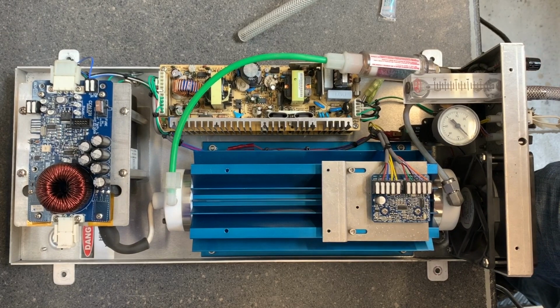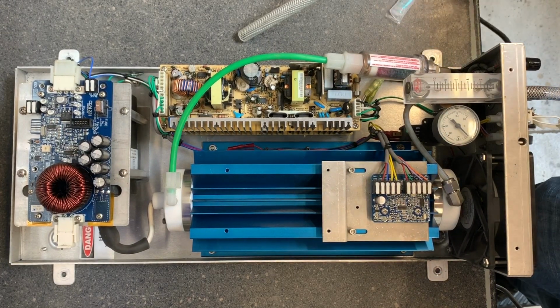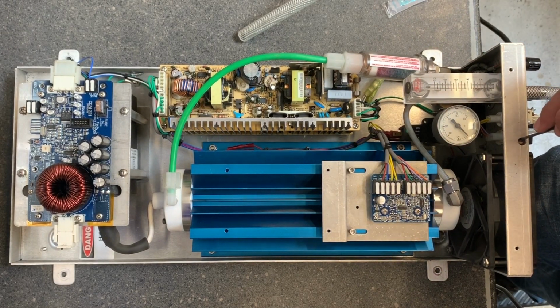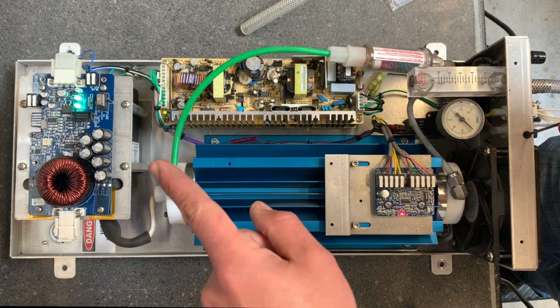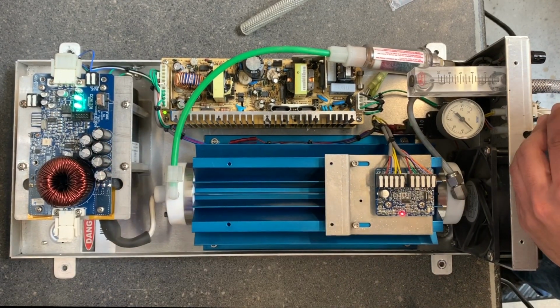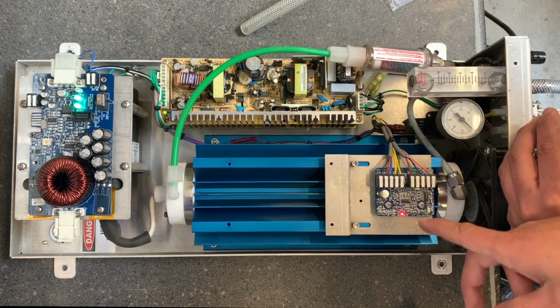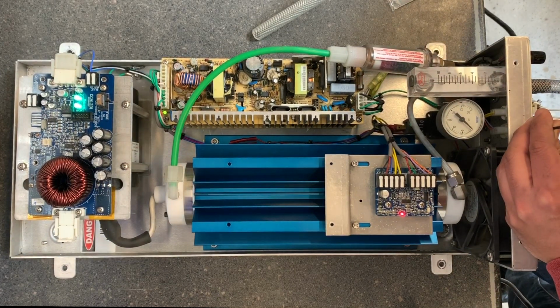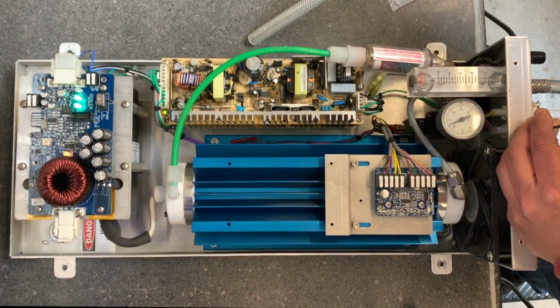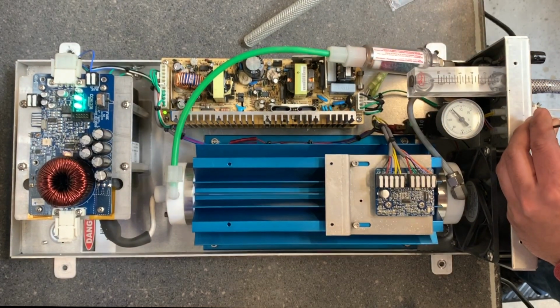So once you give power to the unit, if you have an older unit, you're going to have a cover switch you have to press down on. Your drive boards will get your 2 lights. You have a red light here because you have not satisfied the pressure switch yet. Once you turn on your oxygen concentrator, you satisfy it, and then it'll kick on the drive.